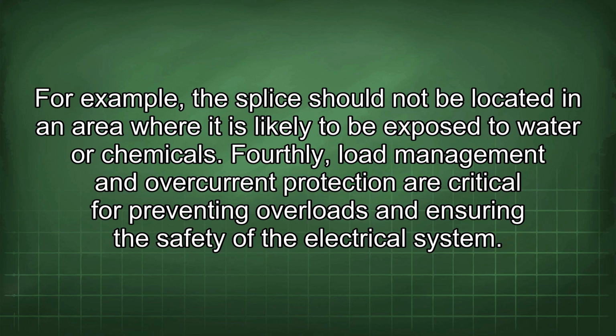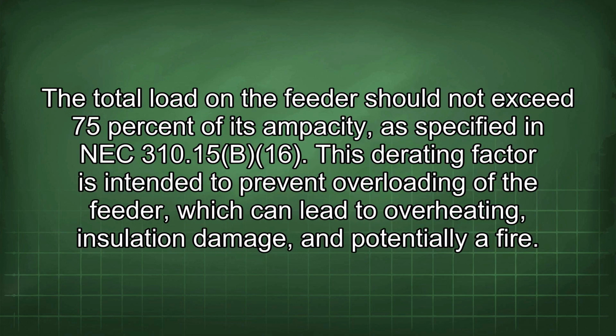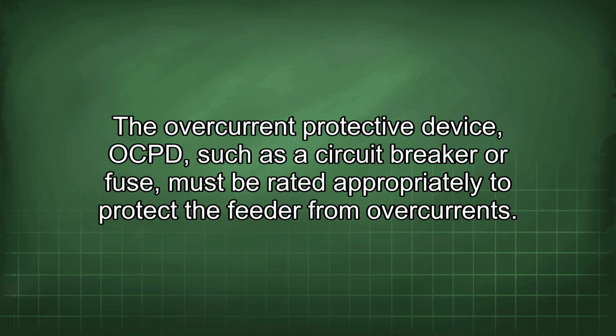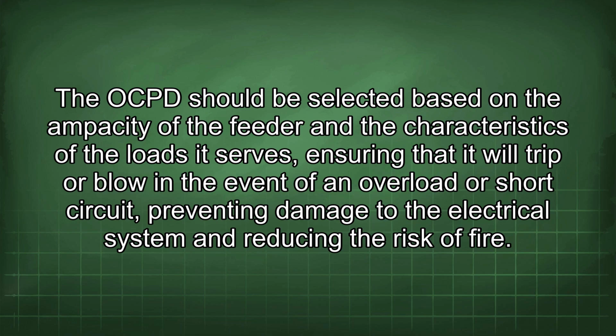Fourthly, load management and overcurrent protection are critical for preventing overloads and ensuring the safety of the electrical system. The total load on the feeder should not exceed 75% of its ampacity, as specified in NEC 310.15(B)(16). This derating factor is intended to prevent overloading of the feeder, which can lead to overheating, insulation damage, and potentially a fire. The overcurrent protective device, OCPD, such as a circuit breaker or fuse, must be rated appropriately to protect the feeder from overcurrents. The OCPD should be selected based on the ampacity of the feeder and the characteristics of the loads, ensuring that it will trip or blow in the event of an overload or short circuit, preventing damage to the electrical system and reducing the risk of fire.